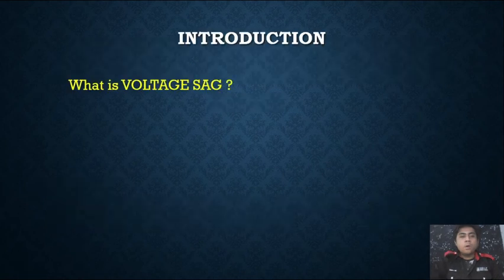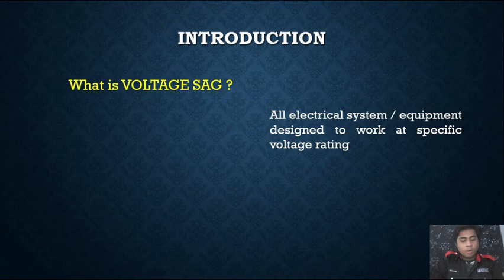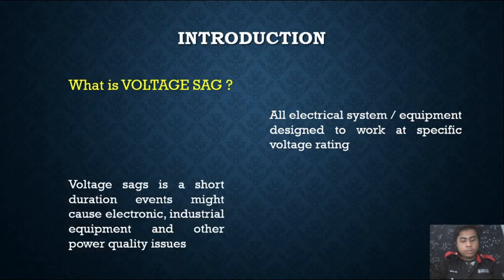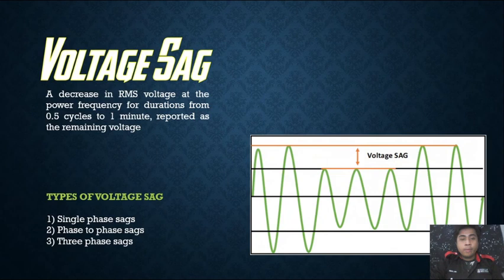Every electrical system or type of equipment is designed to work at a specific voltage rating. Voltage sags are short duration events that might cause damage to electronic or industrial equipment, outages and other power quality issues. By definition, a voltage sag is a decrease in RMS voltage at the power frequency for duration from 0.5 cycles to 1 minute, reported as the remaining voltage.